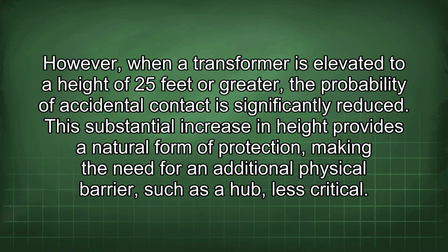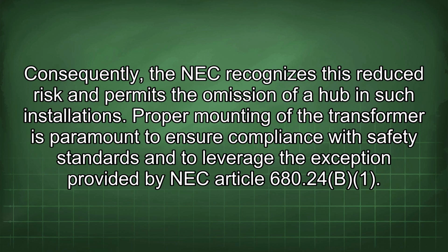equipment. However, when a transformer is elevated to a height of 25 feet or greater, the probability of accidental contact is significantly reduced. This substantial increase in height provides a natural form of protection, making the need for an additional physical barrier, such as a hub, less critical. Consequently, the NEC recognizes this reduced risk and permits the omission of a hub in such installations.